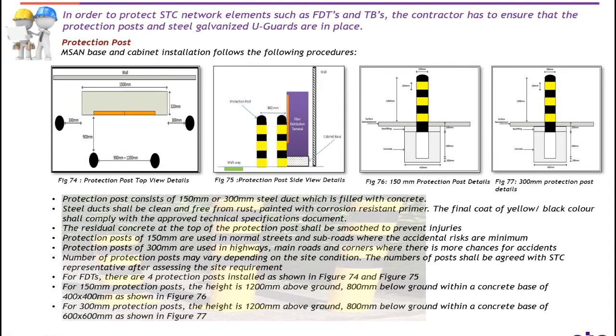Number four: protection posts of 150 mm are used in normal streets and sub-roads where accidents are less likely. Number five: protection posts of 300 mm are used in highways, main roads and corners where there is more probability for accidents. Number six: the number of protection posts may vary depending on the site condition; the number of posts shall be agreed with the STC representative after assessing the site requirements. Number seven: for FDTs, there are four protection posts installed. For 150 mm protection posts, the height is 1.2 meters above ground and 800 mm below ground, with a concrete base of 400 × 400 mm.